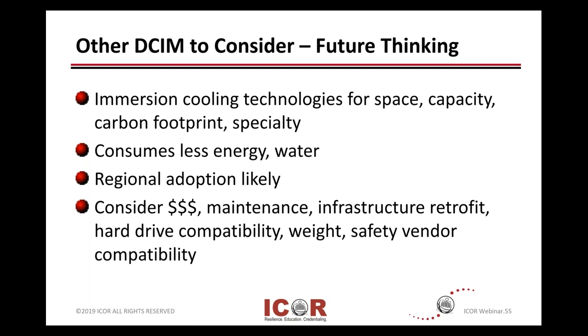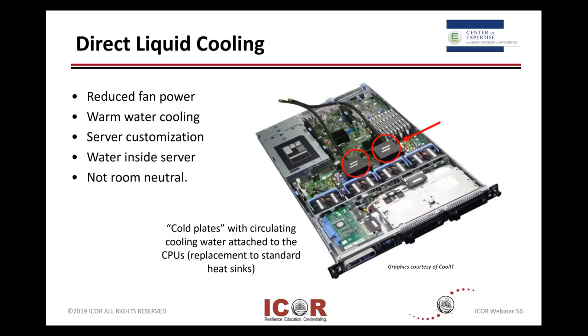There's much more information and deployment where these systems are being used now, not only in the USA but also in Europe and portions of Asia. You can also look at direct liquid cooling, whether that's using some kind of cold plate technology and bringing the coolant directly into the devices. The benefit is you're bringing the cooling right to the source of the heat, which reduces your fan usage and fan power. The challenge is it's a unique server — you're going to spend more money and it's going to be customized.